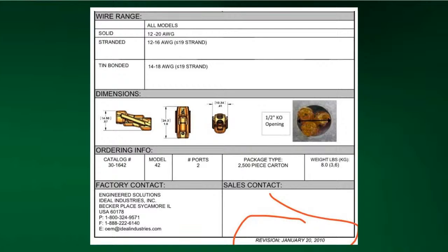We've had this before too, with some of those lit mirrors, crazy mirrors you can install now in hotels and stuff. Let's say you have a conduit coming into that mirror, what you're doing is taking those splices and shoving them back into the conduit, and then you hang the mirror. So the splice isn't inaccessible, it's just shoved back in that raceway a little bit. If you wanted to take that mirror down, you could still access those splices. I think that's what this is about.